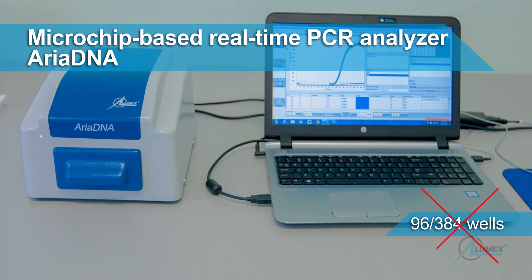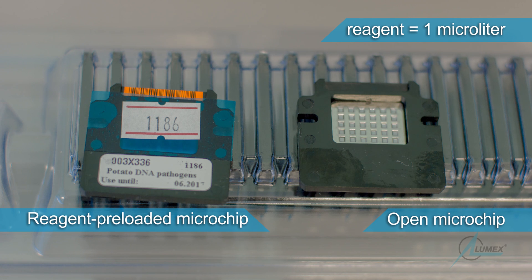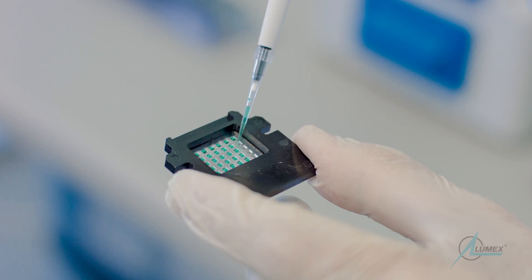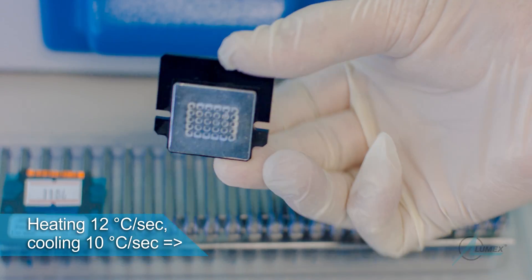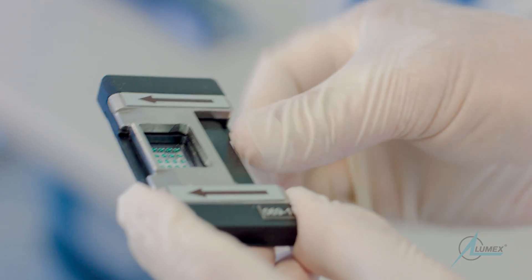AriaDNA is a microchip-based, real-time PCR analyzer. It works with ready-to-use microchips with preloaded lyophilized reagents for dedicated applications, and also allows the use of third-party PCR reagent kits or developing customized assays on empty microchips. The use of microchips offers cost-efficient analysis because of low reagent consumption. Its rapid heating and cooling cycles are contributed by the aluminum base of the microchip, which is a better conductor than polypropylene.